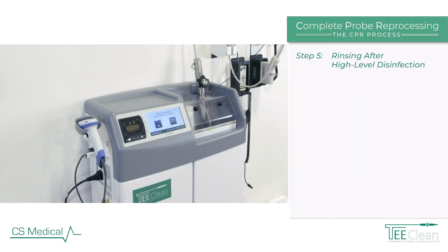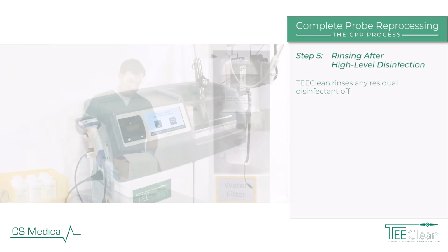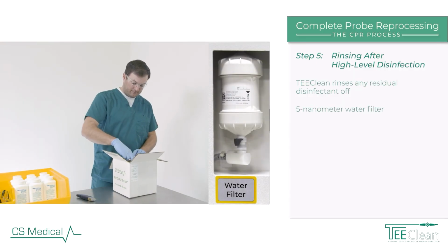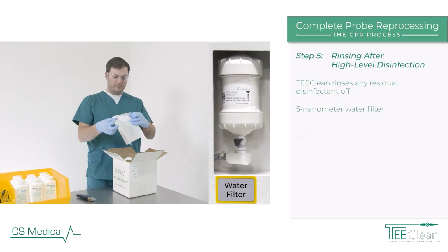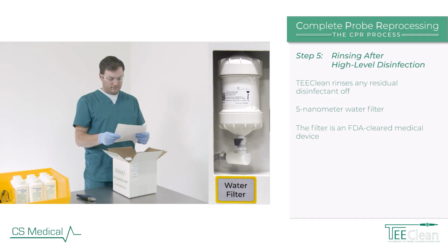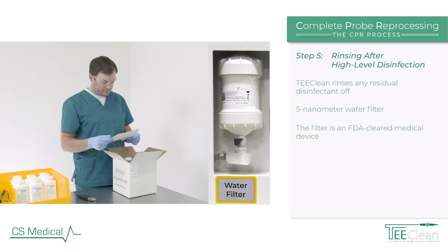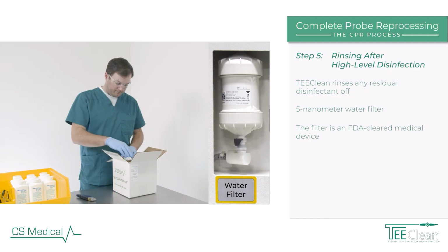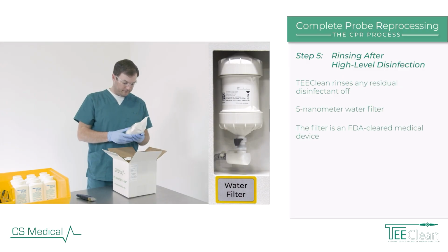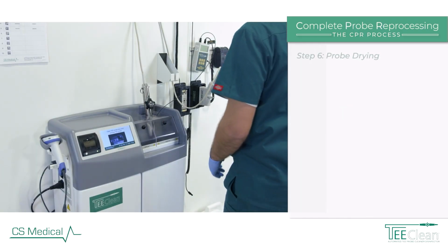Step 5. Rinsing after high-level disinfection. After high-level disinfection, TEEClean rinses any residual disinfectant off before alerting the user a successful disinfection cycle has been performed. TEEClean incorporates a 5 nanometer water filter. The filter is an FDA-cleared medical device that ensures that all water entering TEEClean is filtered to 5 nanometers, retaining bacteria, viruses, and endotoxins.